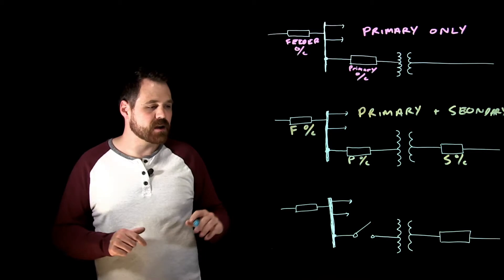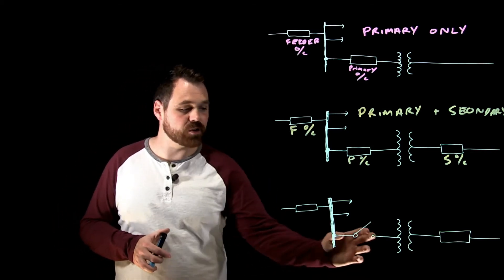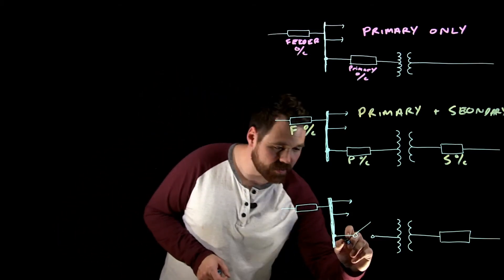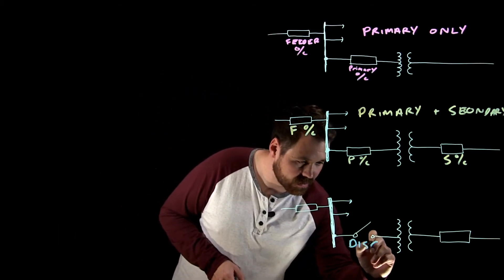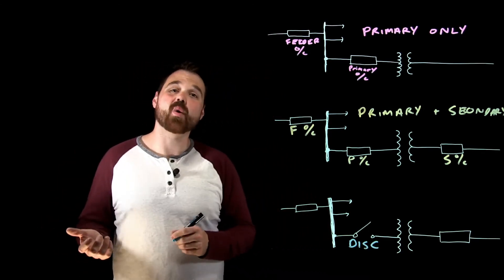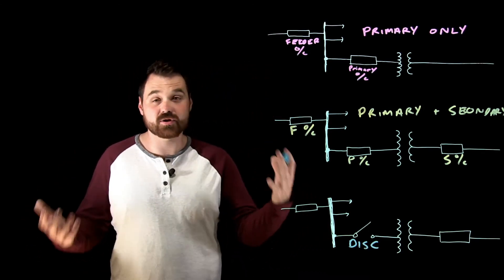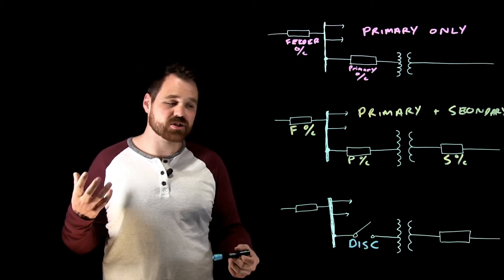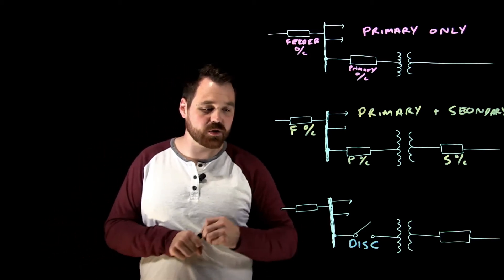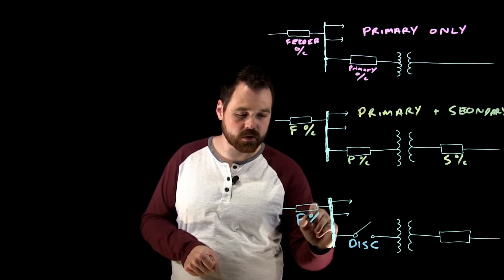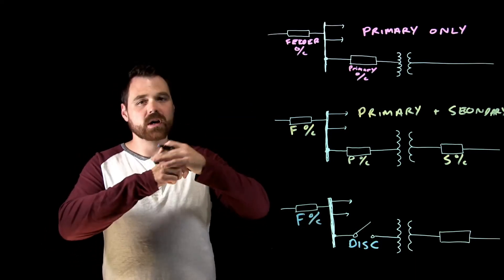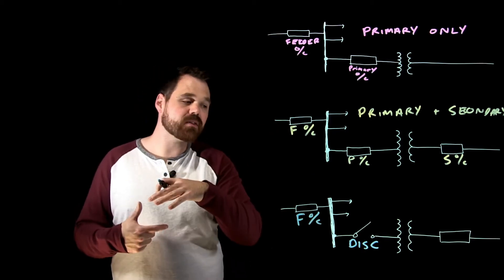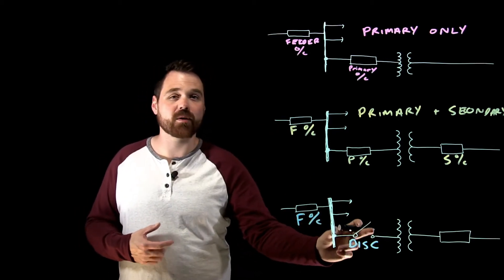The third one is a little bit more of a special application. On the primary, there isn't an overcurrent device — I only see that disconnect. Now a disconnect is required on all transformers by code, so all of these have the disconnect as well. But on this one, there are special certain circumstances where if my feeder OC is sized correctly and within a certain percentage of the rated primary current — if that feeder is small enough — then I don't require overcurrent protection on the primary.